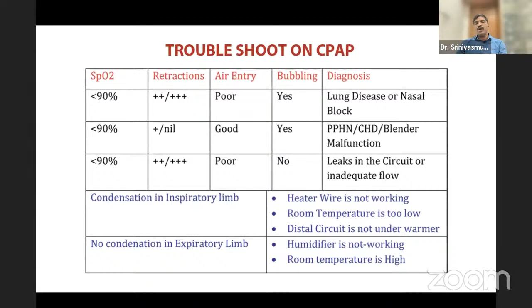If there is no condensation, that means humidification is not adequate. So maybe there is no water in the bubble chamber or jar or humidifier chamber, or your room temperature is very high. That is why there is no condensation in the expiratory limb. So the success formula about CPAP is antenatal steroid, if possible, should be covered. The delivery should preferably be in a tertiary care center so that CPAP and surfactant can be given as early as possible. And early CPAP, early means less than 2 hours. Early could be 5 minutes or 10 minutes, as early as possible.